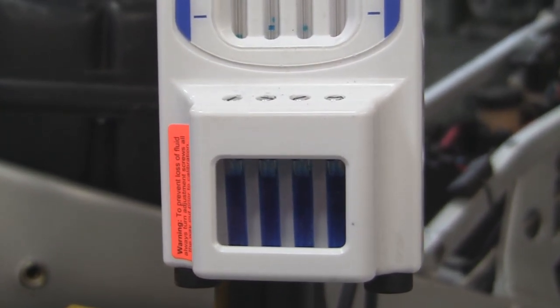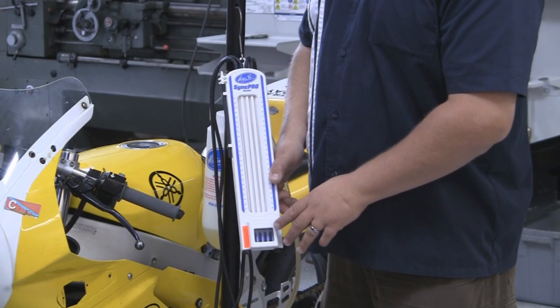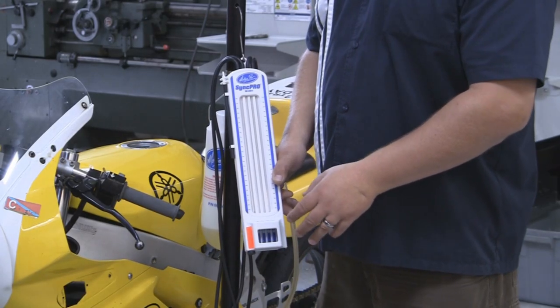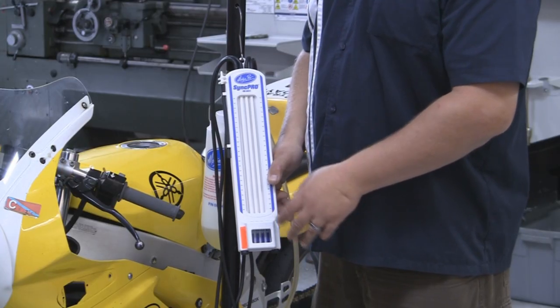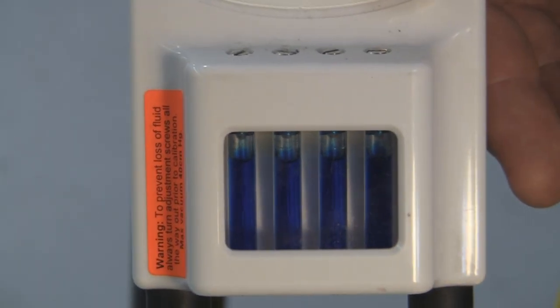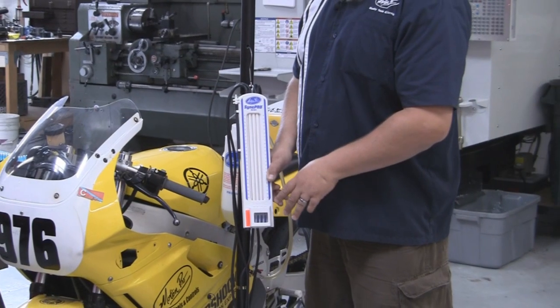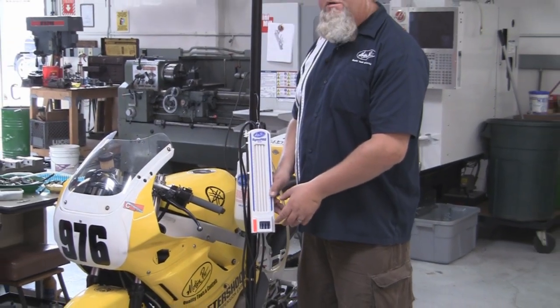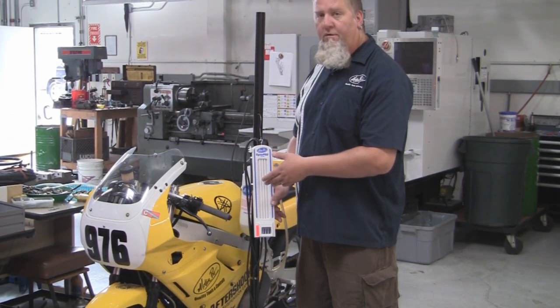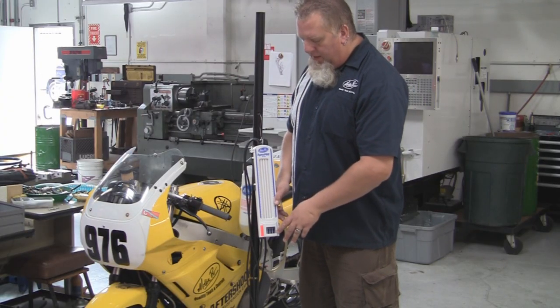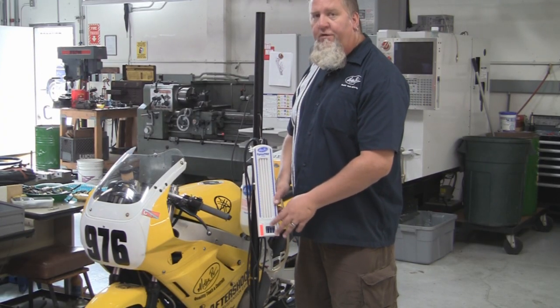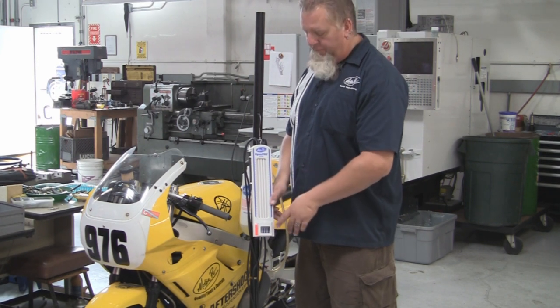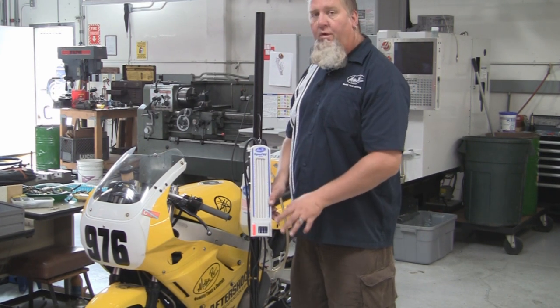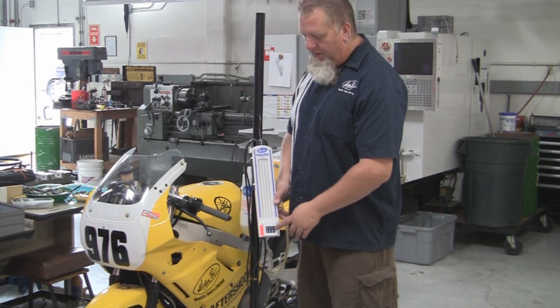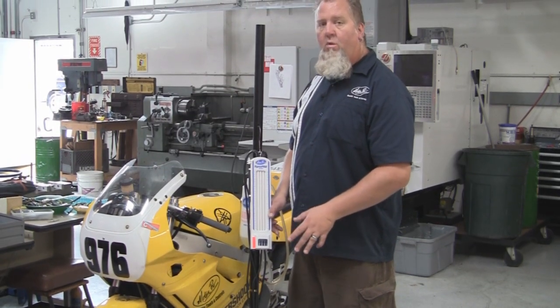They're completely independent. The reservoirs down at the bottom of the tool hold the fluid, the Sync Pro fluid, and the fill level is a really critical part of this tool because the small airspace between the top of the fluid and the bottom of the calibration screw is what actually allows the fluid to move up and down in response to vacuum on the other side. And so the higher the vacuum, the larger that airspace will expand, and the farther the fluid will rise in the columns. If that airspace is too large, then the vacuum limit of the tool is reduced. So that's something to keep a really close eye on with the tool that you have, to make sure that that airspace should only be about 1/4 of an inch.